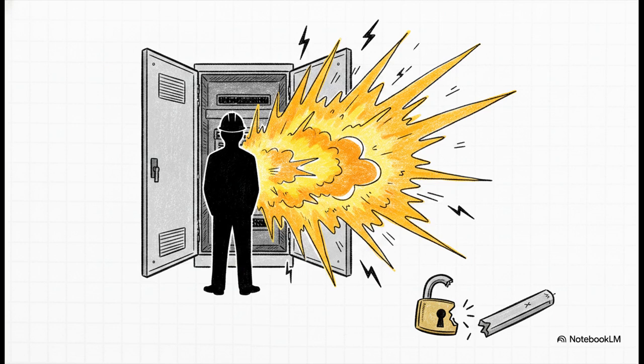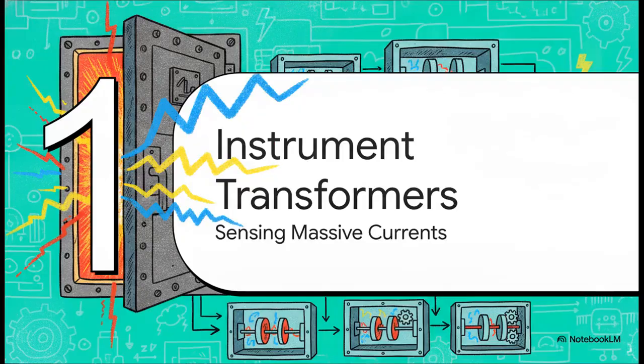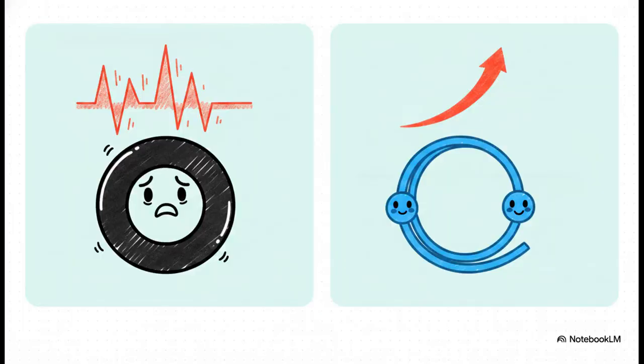Bypassing this interlock is the single most common way engineers get seriously hurt on switchgear. It completely defeats the entire safety architecture. Okay, let's move into our next section. Instrument transformers. We're going to look at sensing massive currents safely and how this whole system actually functions inside a sealed box. So here's a good question. How do we monitor these dangerous currents and feed data to our protection relays if we can't ever get near the live components, since the steel doors have to stay permanently sealed?